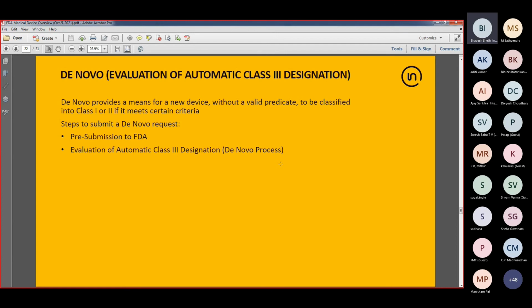If you are required to submit a De Novo application, it's best to start with a pre-submission to the FDA. I'll talk a little bit about the pre-submission in a couple of slides. Eventually, you're going to provide the same amount of information, in fact, a little more than what you provide in a 510K. Of course, you're not comparing against the predicate, but you're still providing test data, device design documents, software documents if applicable, material information. So all the attributes that are applicable for the device, you have to provide supporting information to the FDA, and then they review the De Novo and grant classification and grant the clearance.